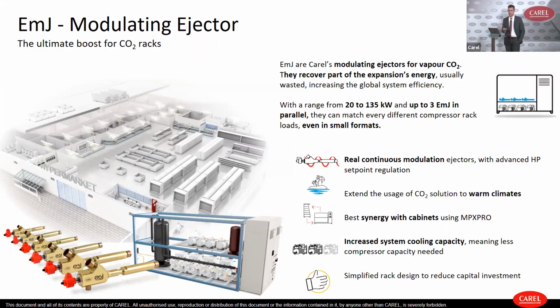And this brings us to think that with ejectors it is possible either to increase the cooling capacity of the unit, or to remove, for example, one compressor in order to reduce the cost of the unit, because you have the ejector that is managing the special transcritical high pressure and high temperature conditions.